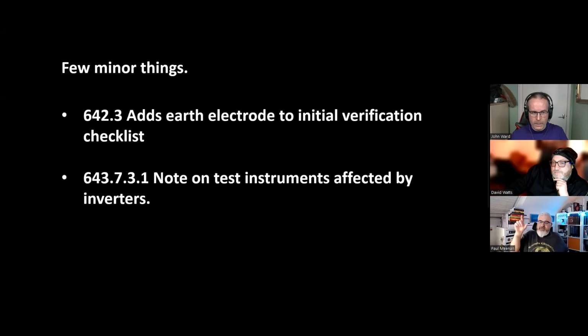Now, I don't know if this is an EMC issue, a compatibility issue, or an earth loop issue, because when I used to do testing, going back 20 years, on inverters, let's say we do Dagenham station. Dagenham had a UPS system, an inverter, and we would do the earth loops with it on bypass. We would switch the inverter in and do the test again to ensure that the disconnection time was still achieved through the inverter.